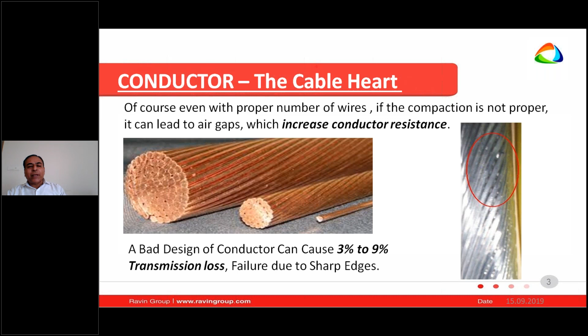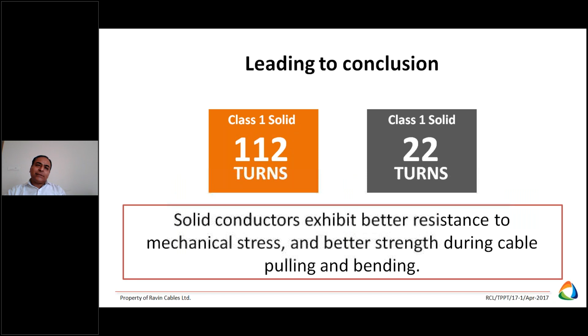If proper geometry is not there, what happens? It leads to localized heating. Suppose compaction is not proper and the geometry is not there, what happens? It leads to hot spots in air gaps and leads to failure. Now moving ahead, the difference between solid and stranded conductor, how, we are not covering today. I am just moving ahead. Solid wires are always better for small cross-section diameters as compared to the stranded conductor.